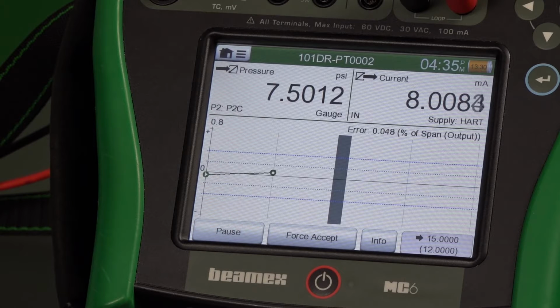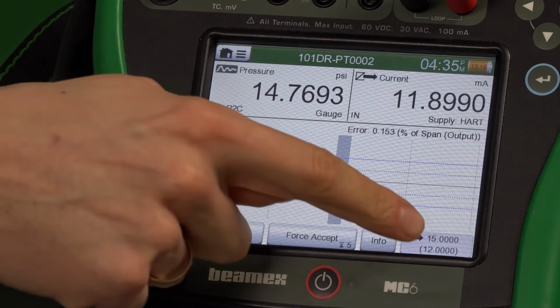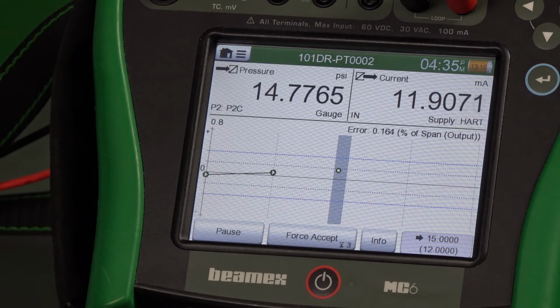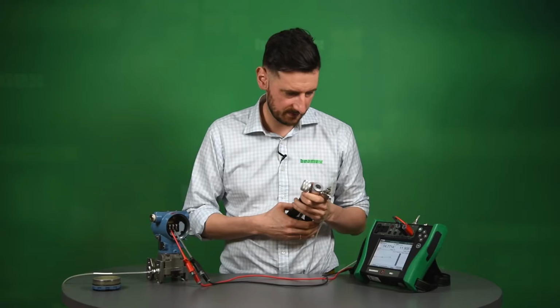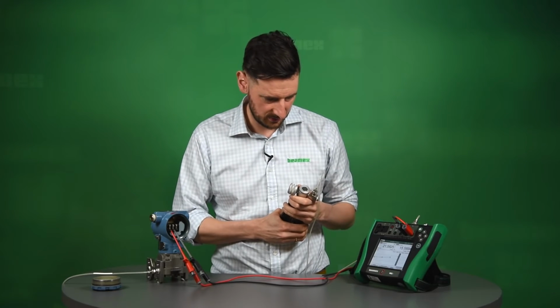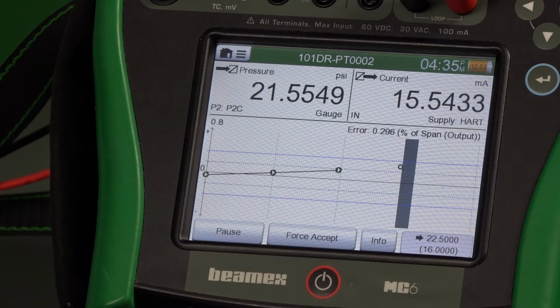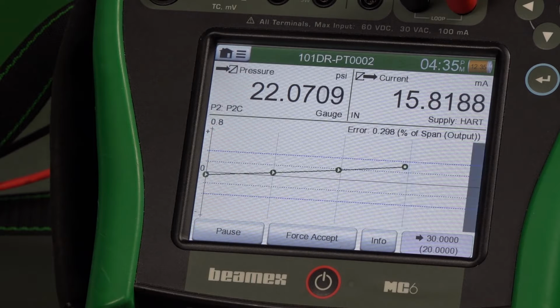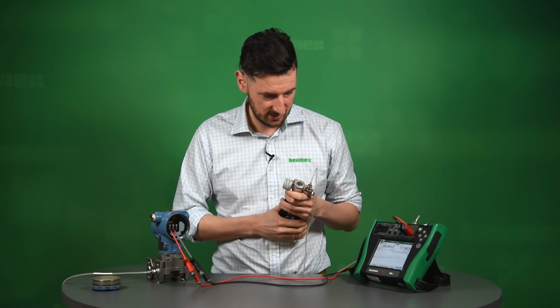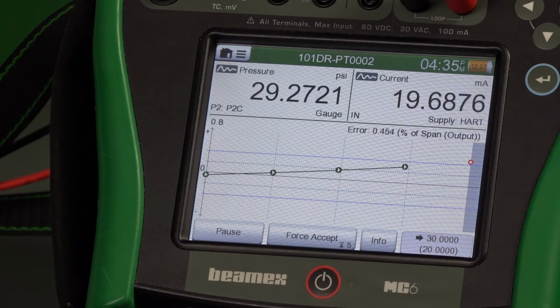Next one is 15, so let's do that. So we're trying to go to 15 or thereabout, and we're expecting 12 milliamps. So we wait for this signal to be stable, and the documenting calibrator just accepted that one. So let's move on to another one. This is 22.5. We're going to pressurize it slightly more, and we're going to leave it there and wait for the documenting calibrator to actually capture that calibration point. And the last point is 30. We just try to go there as well.